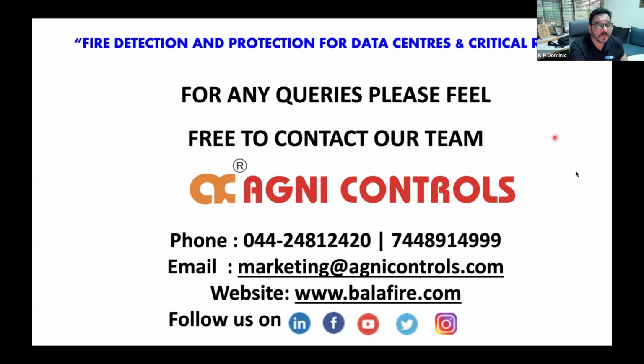Anil Kumar is asking. Go ahead, sorry, Anil. Wherever spot detectors are being used, an additional detection system is also being employed there. For example, as Dominic sir said, in airports it's not just spot detectors. You will also find beam detectors, and in critical areas, you will find both aspiration detectors and flame detectors.